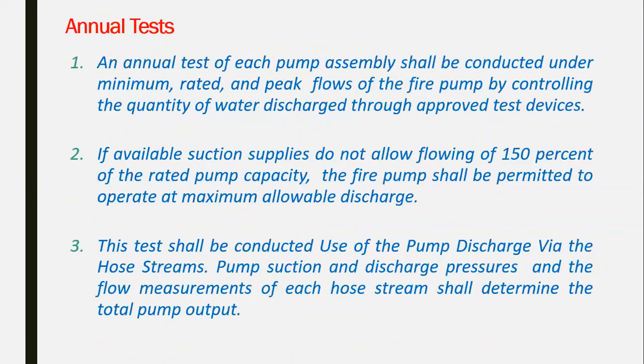What about the annual test? The annual test for each pump assembly shall be conducted under minimum, rated and peak flows of the fire pump. How does it happen? By controlling the quantity of water discharged through the approved test devices. If the available suction supplies do not allow flowing 150% of the rated pump capacity, the pump shall be permitted to operate at the maximum allowable discharge. So here we allow the pump to go with the maximum allowable discharge at full capacity.